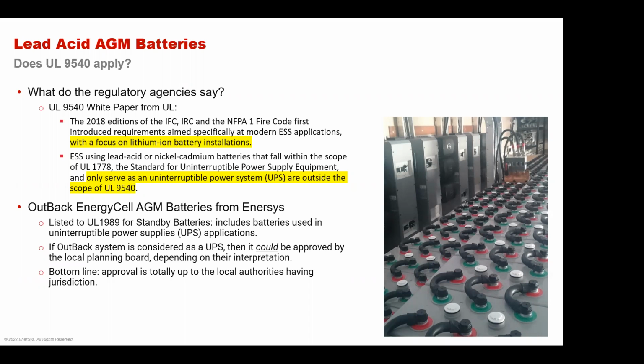And when we're going to be able to add stack batteries on our system, when we do that, we will have a UL 9540A test report done, and we're pretty sure it's going to look very good. There shouldn't be an issue adding more batteries. They just want to make sure that this additional testing is done, that when they force a thermal runaway condition, it doesn't spread, it doesn't catch on fire, and it doesn't emit explosive gases. It's all for the protection of the consumer. So, check with your local authority. They're the ones that are going to tell you whether that's allowed or not.